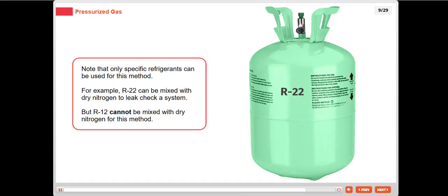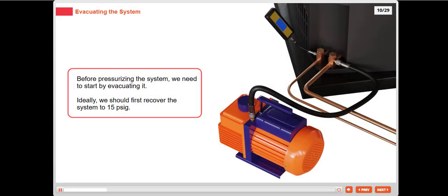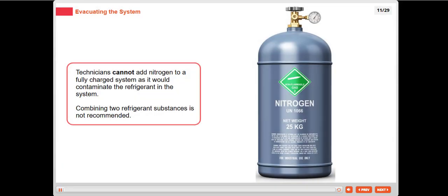Before pressurizing the system, we need to start by evacuating it. Ideally, we should first recover the system to 15 pounds per square inch gauge. Technicians cannot add nitrogen to a fully charged system as it would contaminate the refrigerant in the system. Combining two refrigerant substances is not recommended.